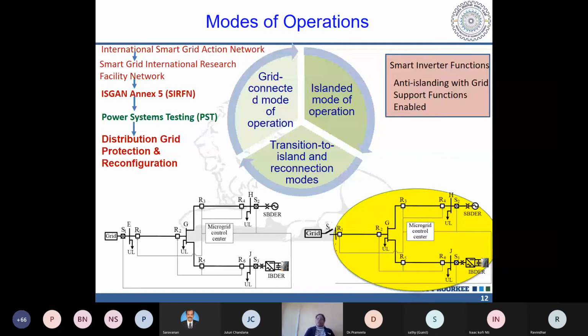And when the grid is off, the control strategy will be something else. Why? Because when the grid is connected, mostly the inverter's control strategy takes the reference voltage and frequency from the grid. When the grid is disconnected, their frequency and voltage will be something different, and their control strategy should switch over. So they should know the status of the main grid. That is one aspect. And therefore, this anti-islanding support with the grid support function should be enabled within the inverter of the renewable sources. Okay, so there are so many things I just told you why this mode of operation is essential.